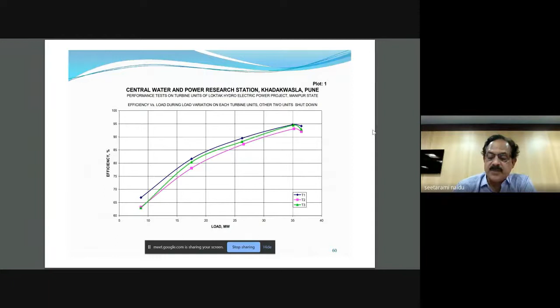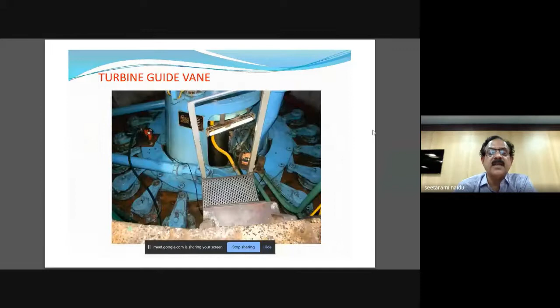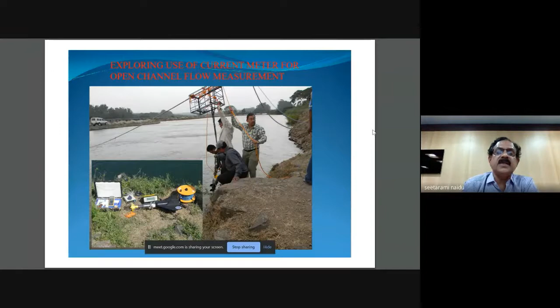This is the individual hydraulic performance of the turbines, you can see. This is a hydroelectric program we have done recently. We have explored the use of current meters for flow. As I was discussing earlier, there was no accessibility to the water conductor system, the penstock. We explored in a rough, unlined canal, at the tail race, the use of current meters. With a single current meter, we explored the discharge with the velocity area method, and this turbine has gone for R&M, with our figures as you can see.